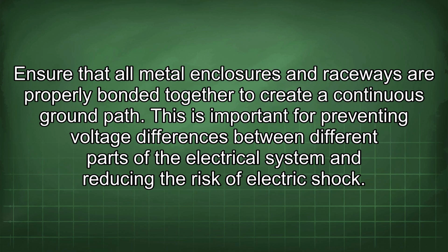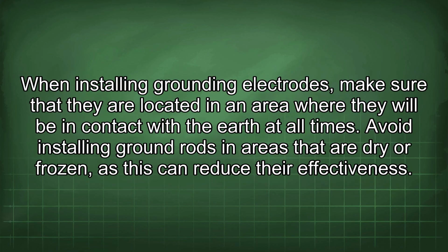Ensure that all metal enclosures and raceways are properly bonded together to create a continuous ground path. This is important for preventing voltage differences between different parts of the electrical system and reducing the risk of electric shock. When installing grounding electrodes, make sure that they are located in an area where they will be in contact with the earth at all times. Avoid installing ground rods in areas that are dry or frozen, as this can reduce their effectiveness.